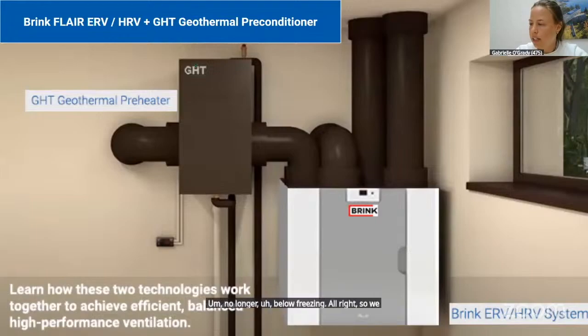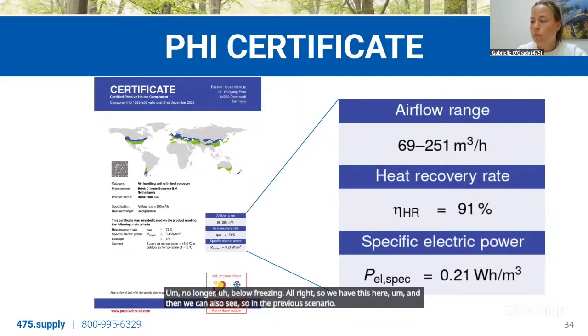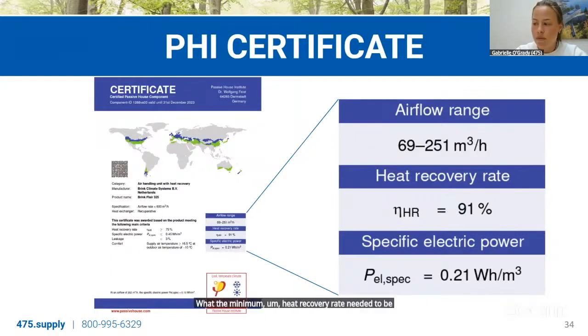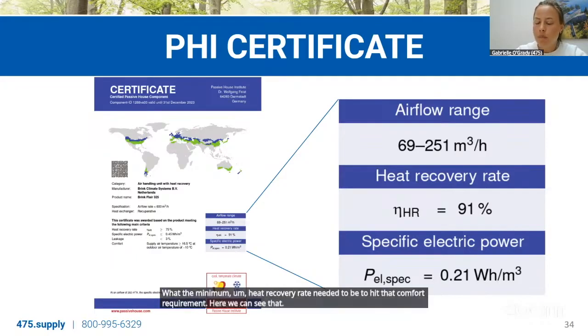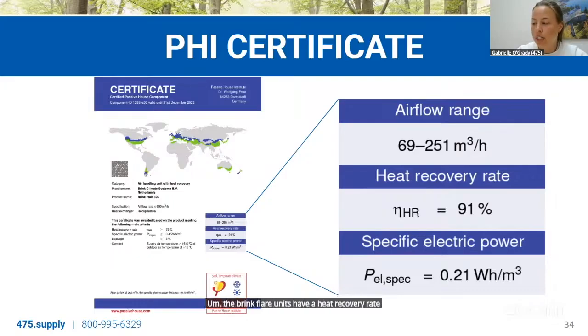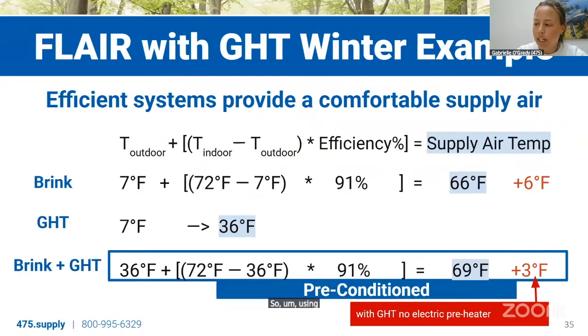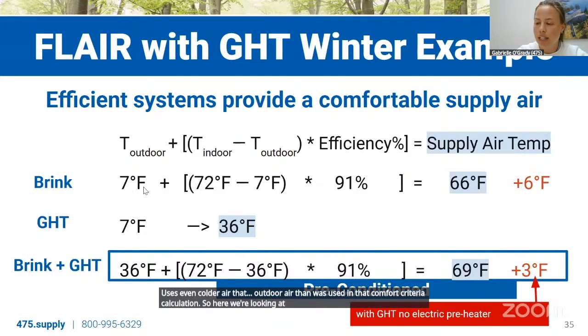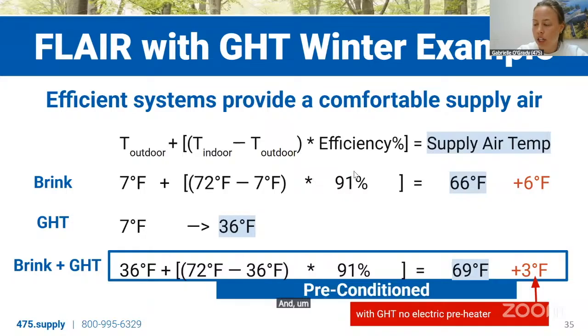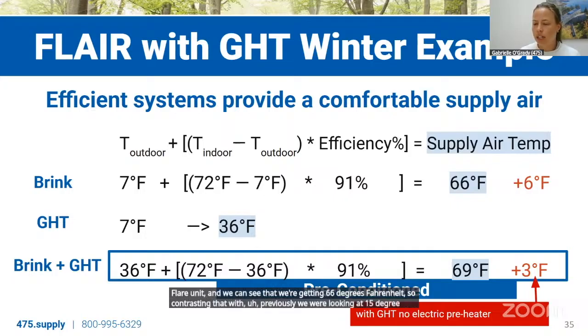All right, so we have this here. In the previous scenario, we saw what the minimum heat recovery rate needed to be to hit that comfort requirement. Here we can see that the Brink FLAIR units have a heat recovery rate of up to 91%. Using that same equation, we can calculate this situation, which uses even colder outdoor air than the comfort criteria calculation. Here we're looking at 7 degree Fahrenheit outside air, and using our highly efficient FLAIR unit we get 66 degrees Fahrenheit. Contrast that with previously, when we were looking at 15 degree Fahrenheit air and only getting 63 degrees supply air temperature. So a difference there.